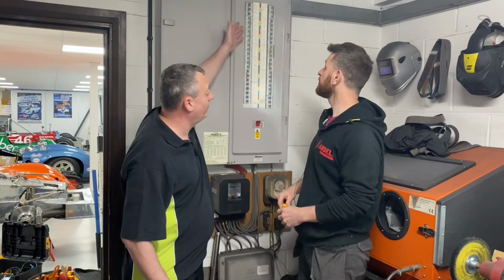Yes, yeah. So it's a three-phase experience that maybe our learners don't always get hands-on. We've got permission to isolate the supply here, and we're going to go through it in the correct process, which means we're going to knock off the breakers first, before doing the main switch. We're going to remove the cover, and then show first the external earth fault loop impedance and then the prospective fault current.